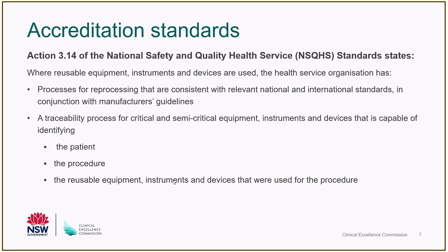When they developed version 2 of the national standards, they removed a lot of the duplication. Everybody has their primary standard, but there are other parts of the standards you need to look at to see what else you need to comply with. So even though 3.14 on reprocessing is in the preventing and controlling healthcare associated infection standard, you also need to look at the clinical governance standard, which covers incidents and quality management systems, and the partnering with consumers standard, ensuring safe patient care, because reprocessing is a critical part of the patient safety program. So you need to look at those other standards, not just 3.14, to determine whether you're compliant.